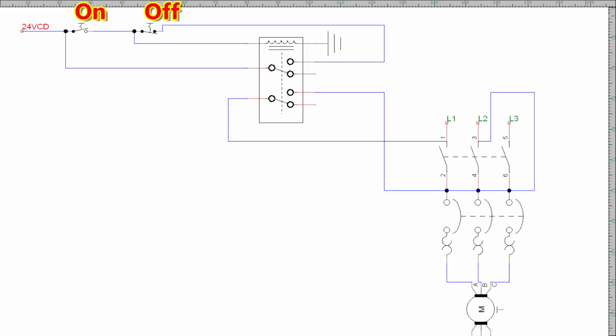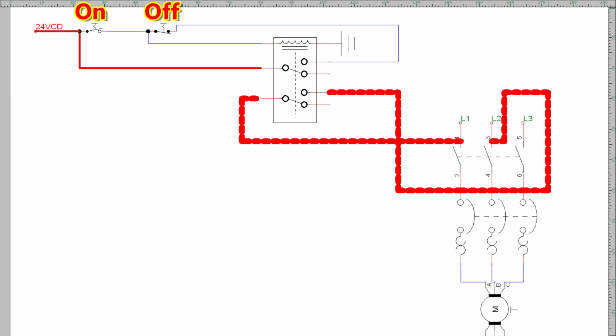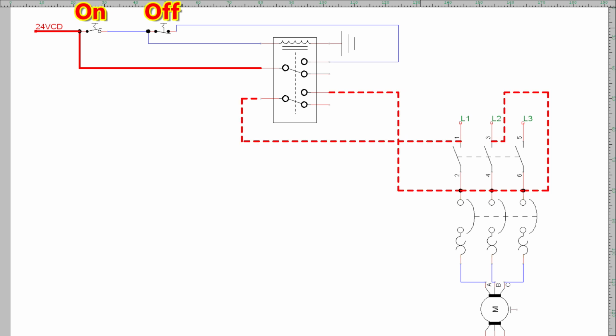Here's the schematic of the machine as it's currently wired. There is no e-stop switch currently. There's a normally open on switch and a normally closed off switch at the top of the page, clearly labeled. Then you have the contactor, the relay that's going to control the contactor, and the motor. This solid red line represents the control voltage when the machine is at rest. This is 24 volts DC. These dashed red lines represent the high voltage in the box as the machine is at rest.